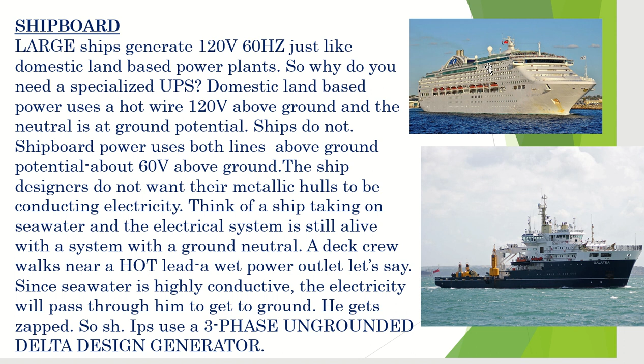We will see ships like this using three-phase currents. For battlefields, ships with these designs can also tolerate a single phase-to-hull short and continue operating. The AC power in most ships is distributed by a three-phase, three-wire 450 volt system. The single-phase transformers step the voltage down to 117 volts. These transformers are connected delta-delta. With the delta-delta configuration, the load may be a three-phase device connected to all phases, or it may be a single device connected to only one phase in navy ships.